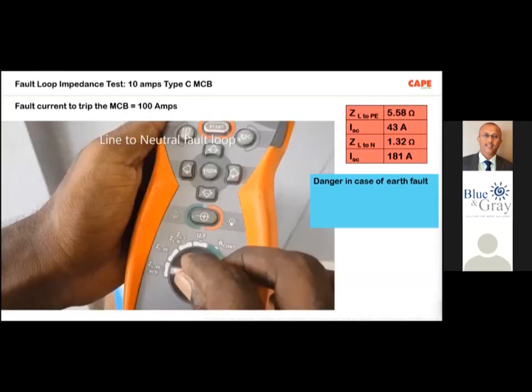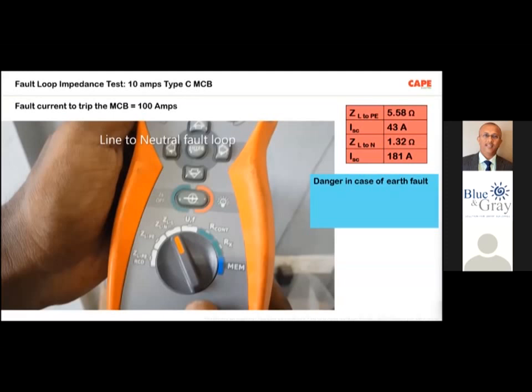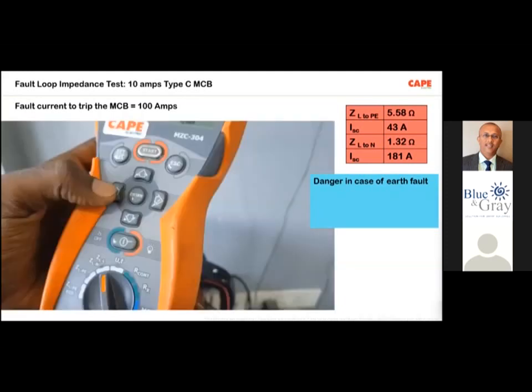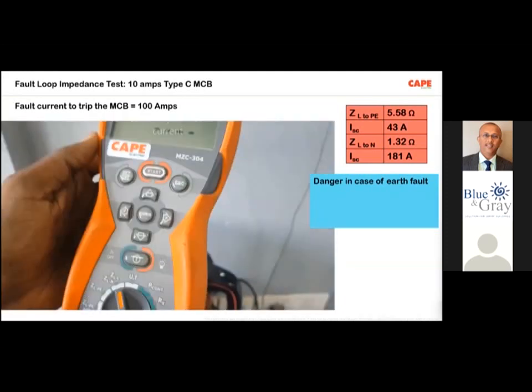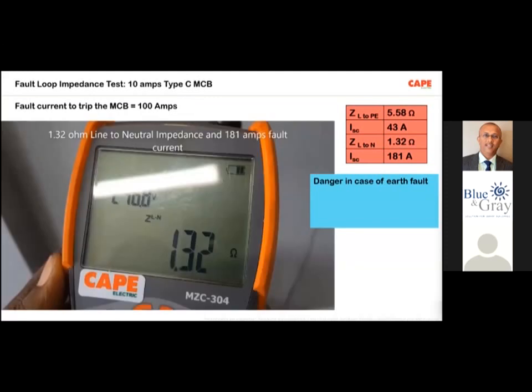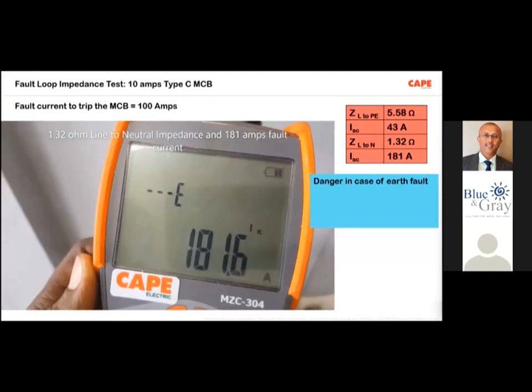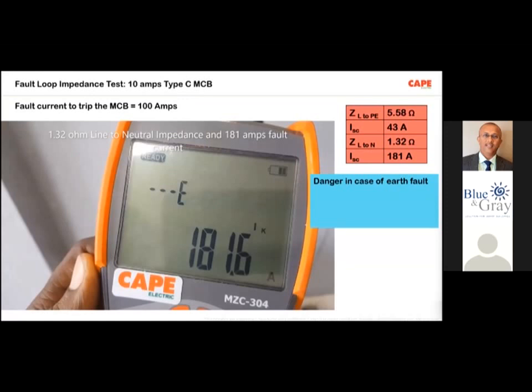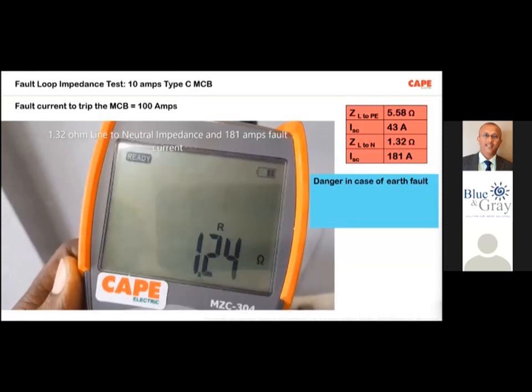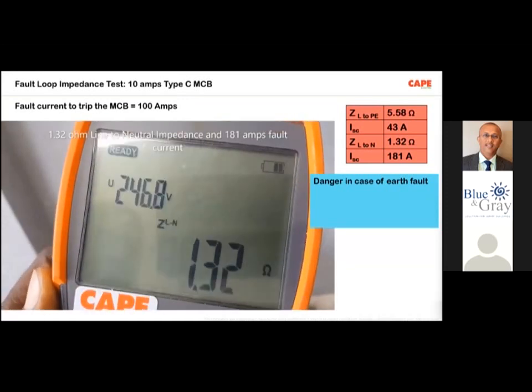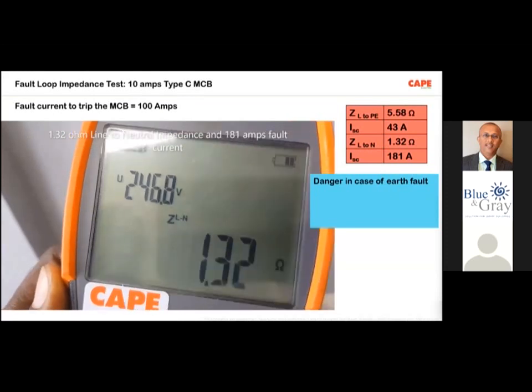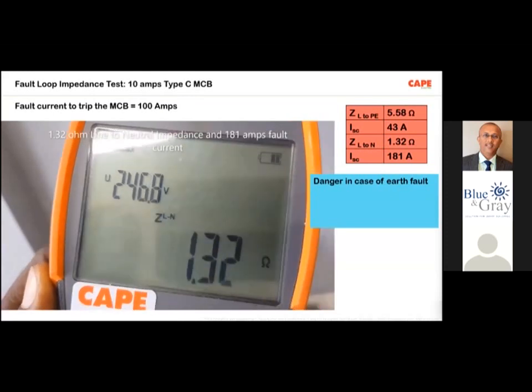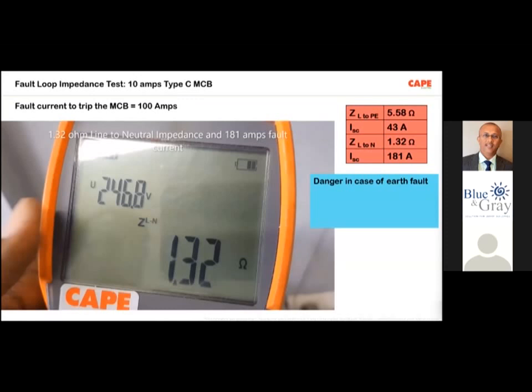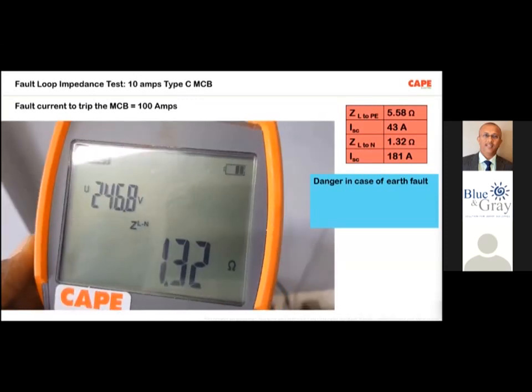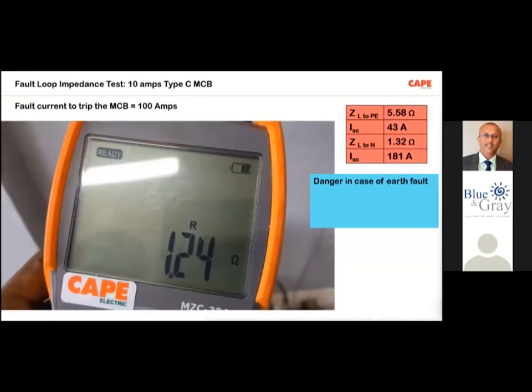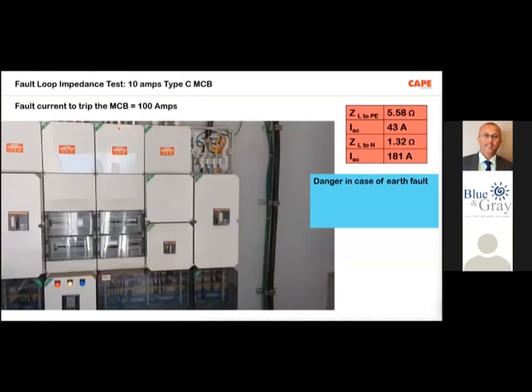Now the same circuit we are testing with line to neutral. In the line to neutral, the short circuit loop impedance is 1.32 ohm, and the current is about 181 ampere. Of course, it is safe. This particular device will trip very easily. Now, why is this happening? Because this particular installation is a TT system, a TT network.